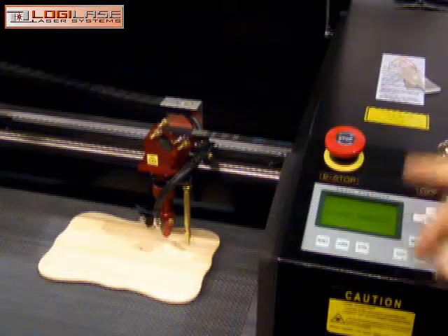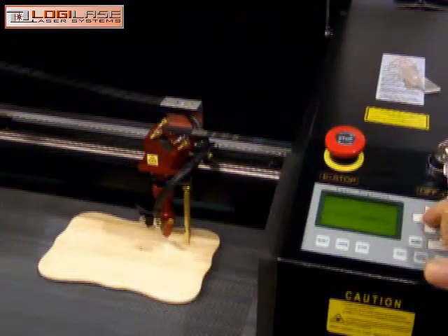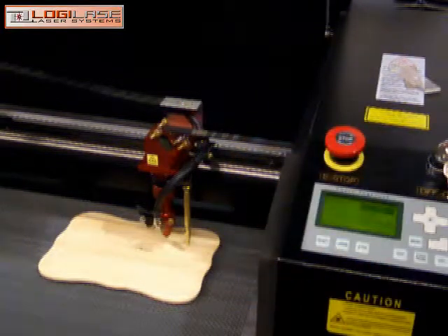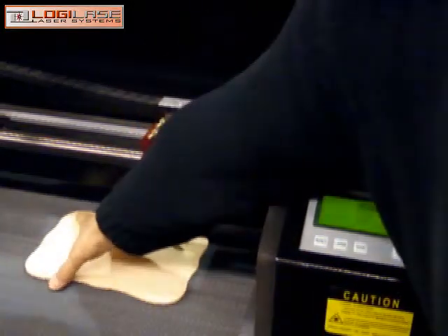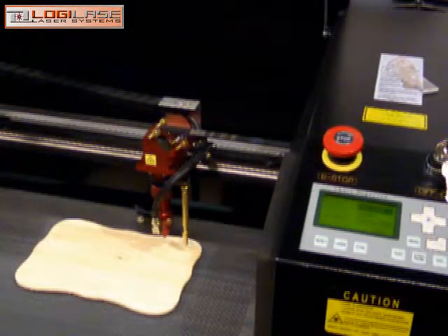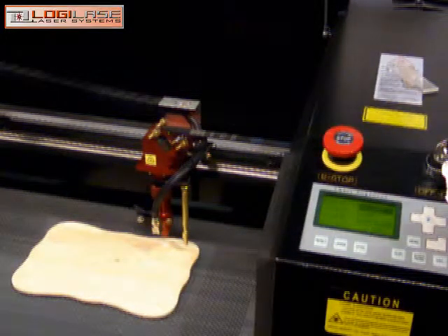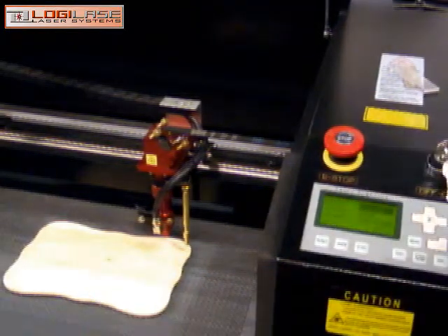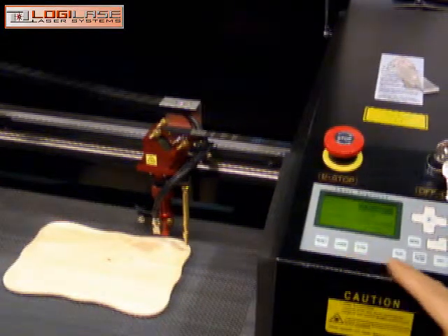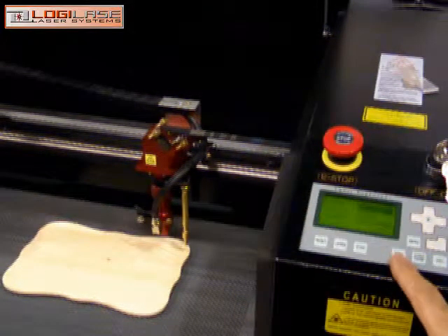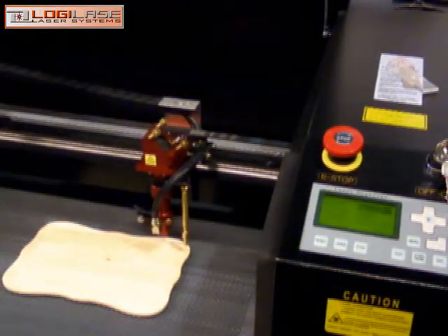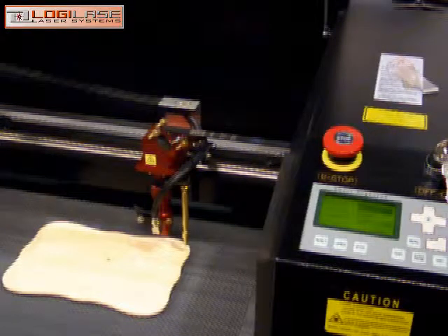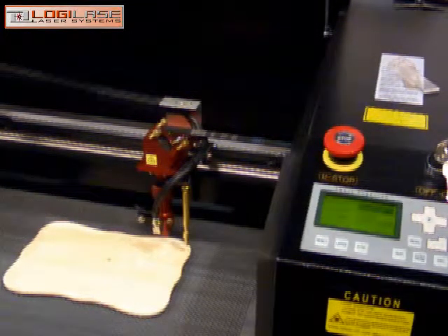surface. So after we did our autofocusing, we go out of Z-axis mode. We are now in screen mode. As long as we don't want to move the head, it doesn't matter, we can keep the same screen mode. So our job is starting from the top right corner. You will get some more details in software operation. What I need to do is bring the position of the material to the top right position of my graphic. So when I press test in this position, it moves like a rectangle. It's the maximum rectangular area you require for that particular graphic.